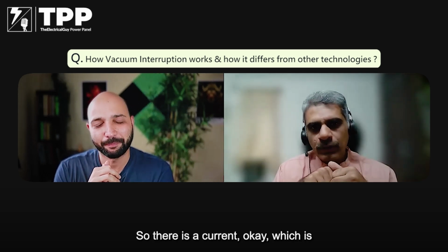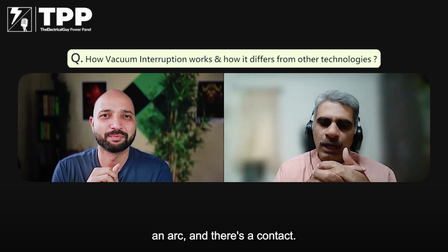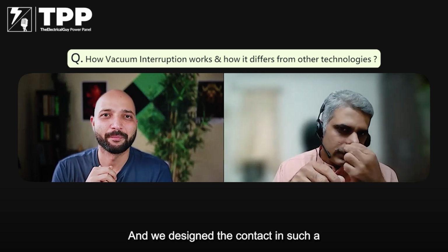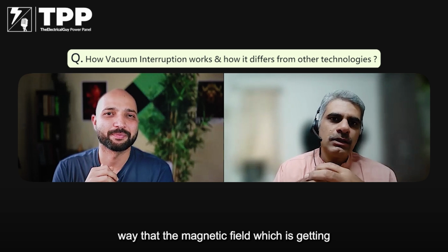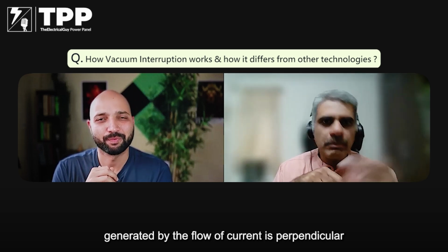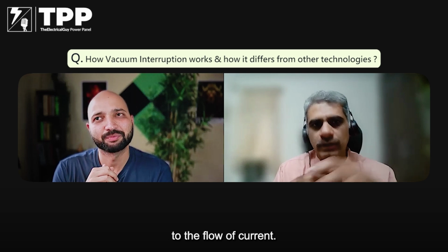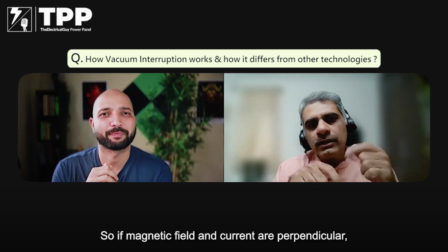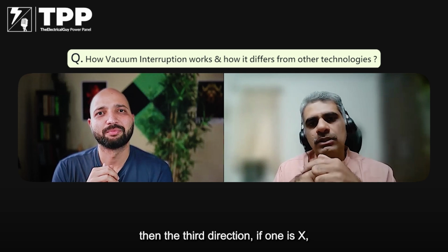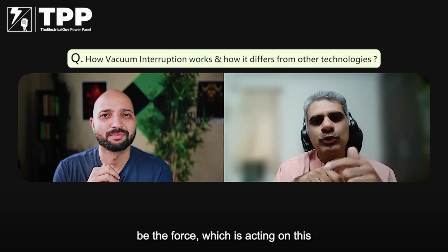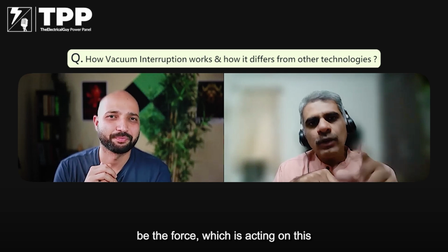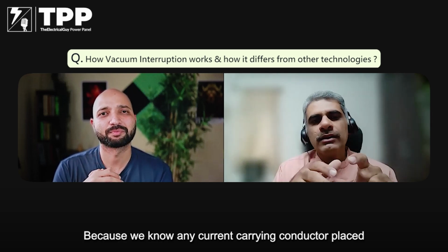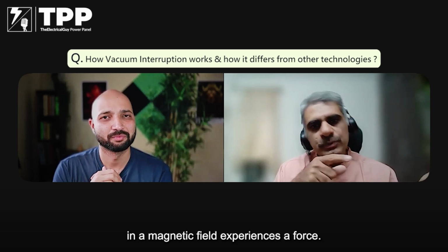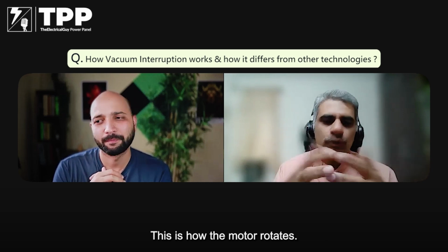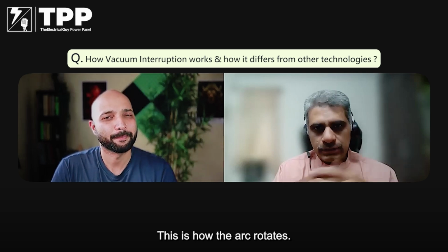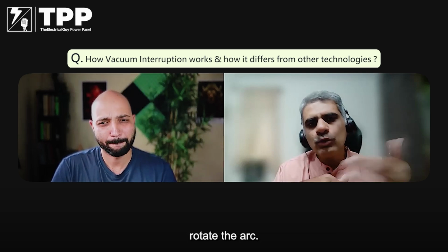So there's a current flowing in the form of an arc, and there's a contact, and we design the contact in such a way that the magnetic field which is generated by the flow of current is perpendicular to the flow of current. So if magnetic field and current are perpendicular, then the third direction, if one is x and the second is y, then the z direction would be the force acting on this conductor, because we know any current carrying conductor placed in a magnetic field experiences a force. This is how the motor rotates. This is how the arc rotates. We use this principle or this phenomenon to rotate the arc.